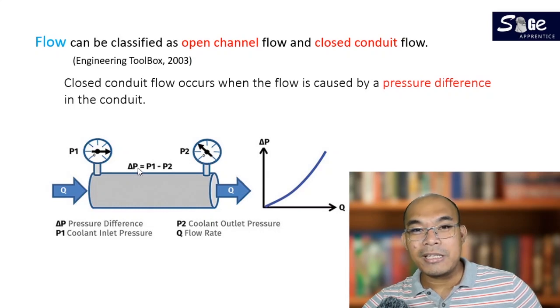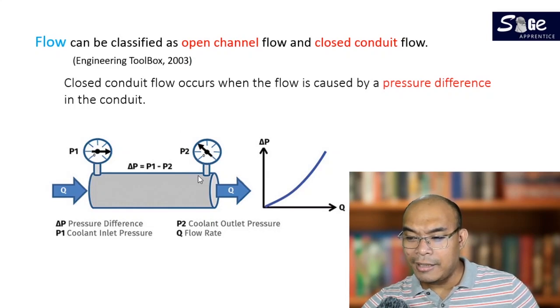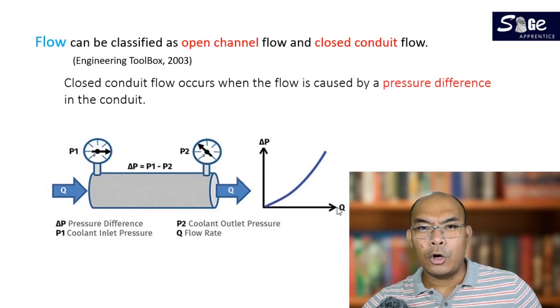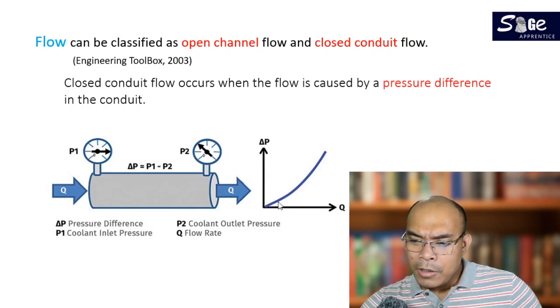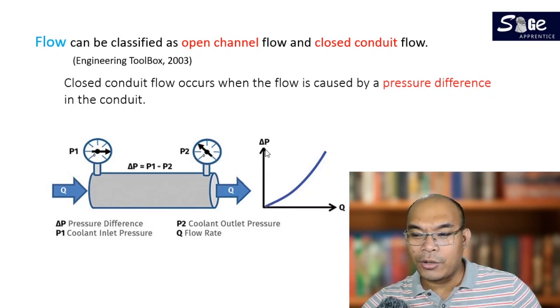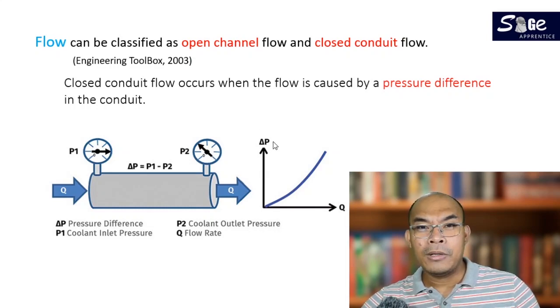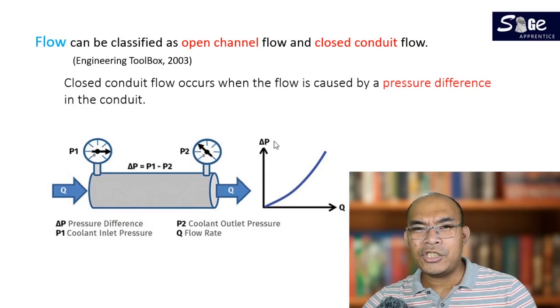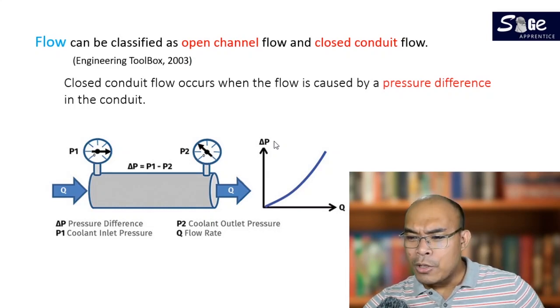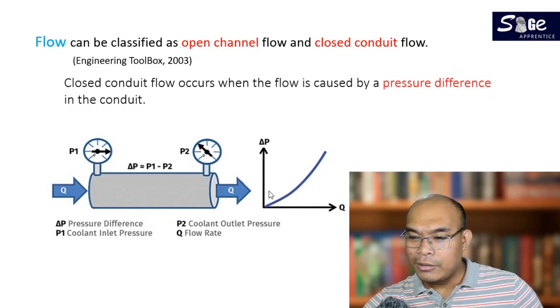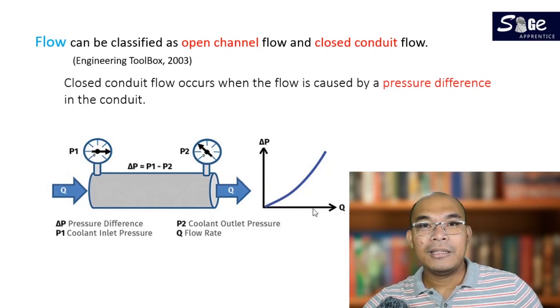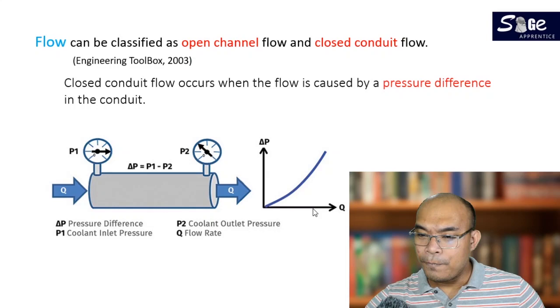The difference between the two pressures is indicated by delta P, where delta P is equal to the pressure at the inlet minus the pressure at our outlet. The relationship, as indicated in this graph, is directly proportional. Although it is not linear, if there is an increase in the differential pressure — delta P indicating differential pressure, meaning the difference between two pressure measurements — the higher the differential pressure, the higher the flow rate, or the higher the Q.